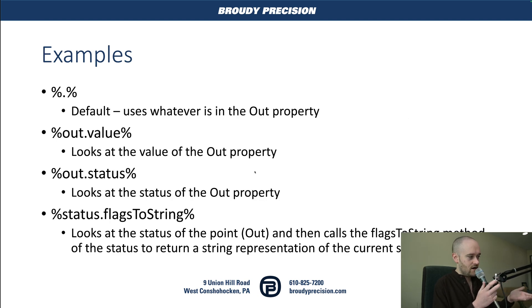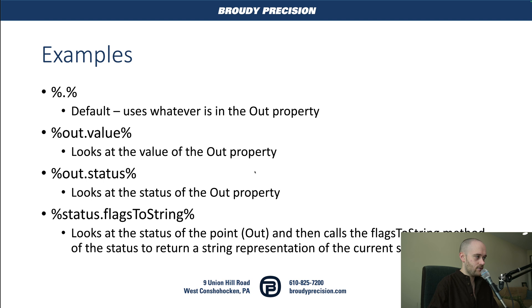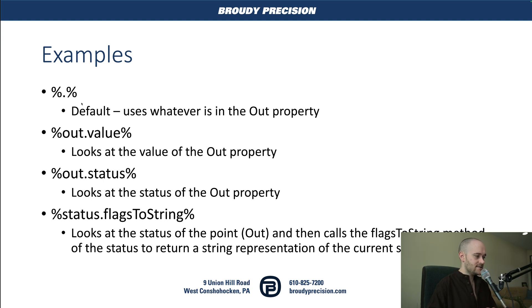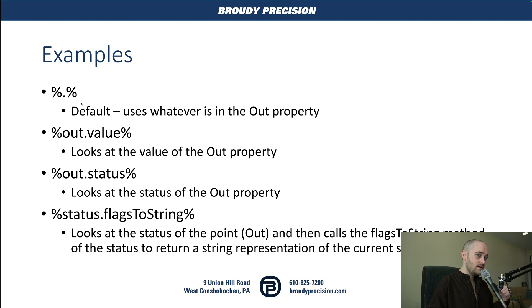You can keep going basically an unlimited number of times. These examples come out of the Niagara documentation on using B Format. The default — percent sign, dot, percent sign — is going to show you whatever the out property is of the point or object you're looking at. Typically it has way more information than you want, so you narrow it down with something like out.value, which looks specifically at the value of the out property.